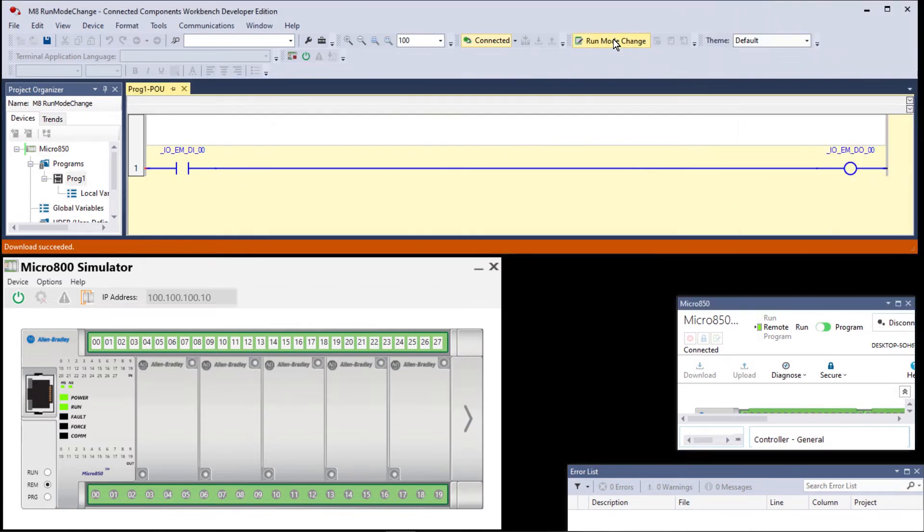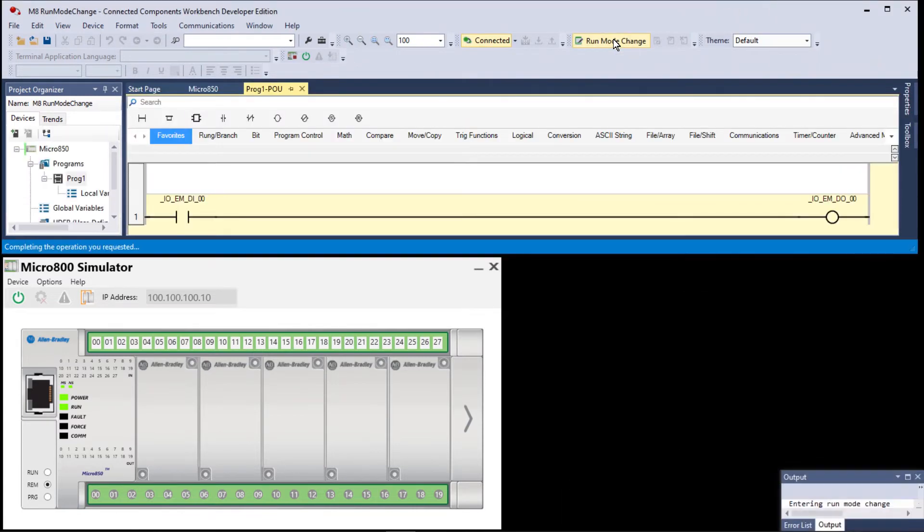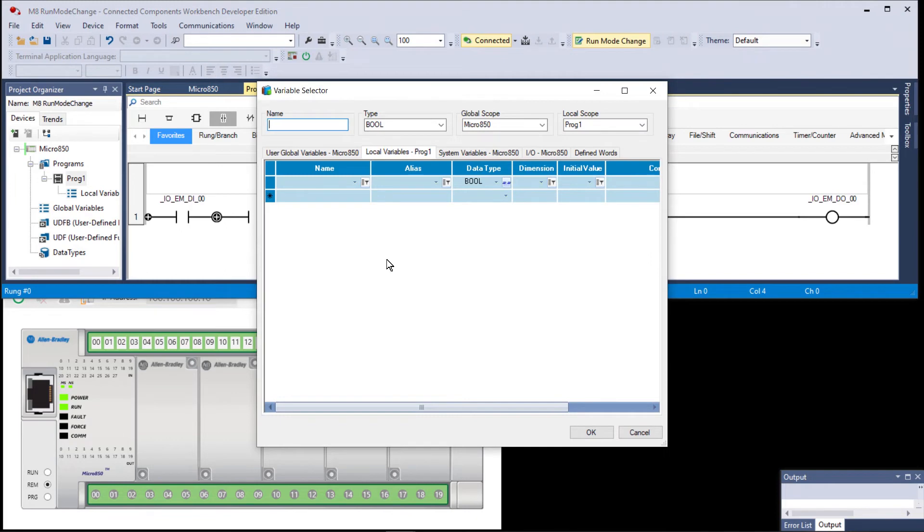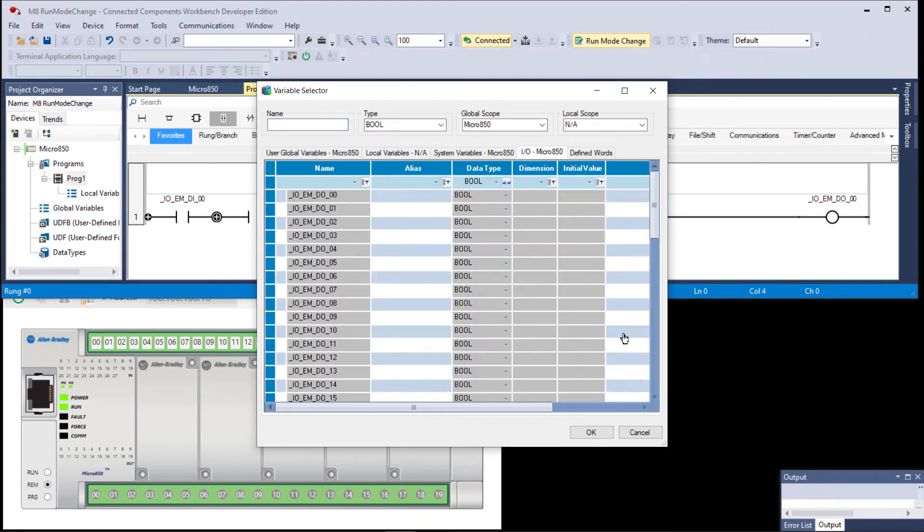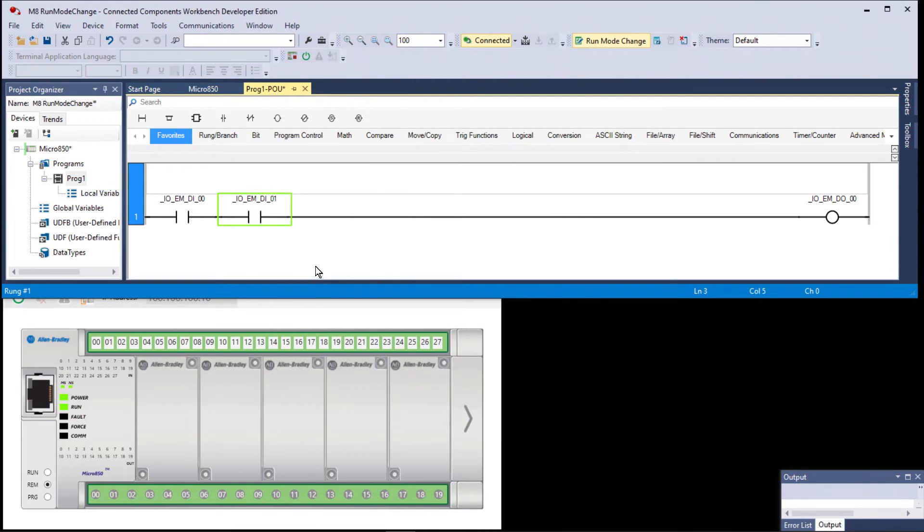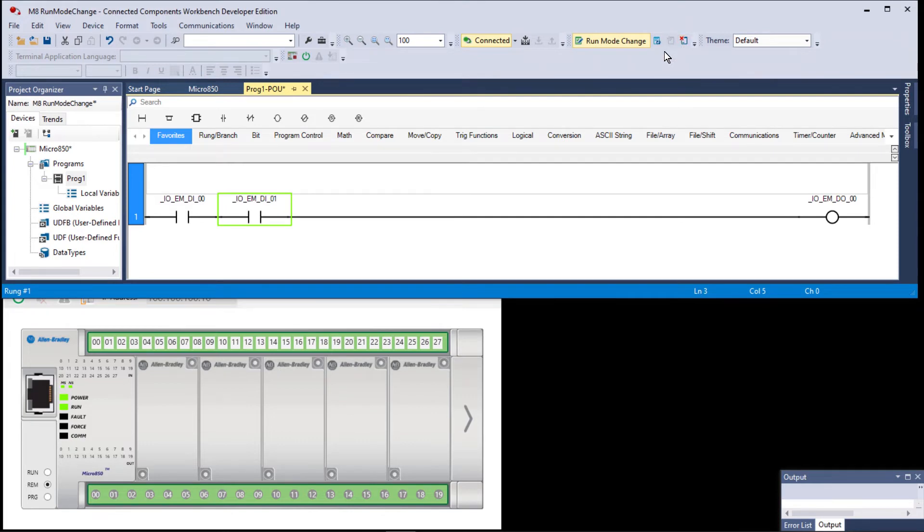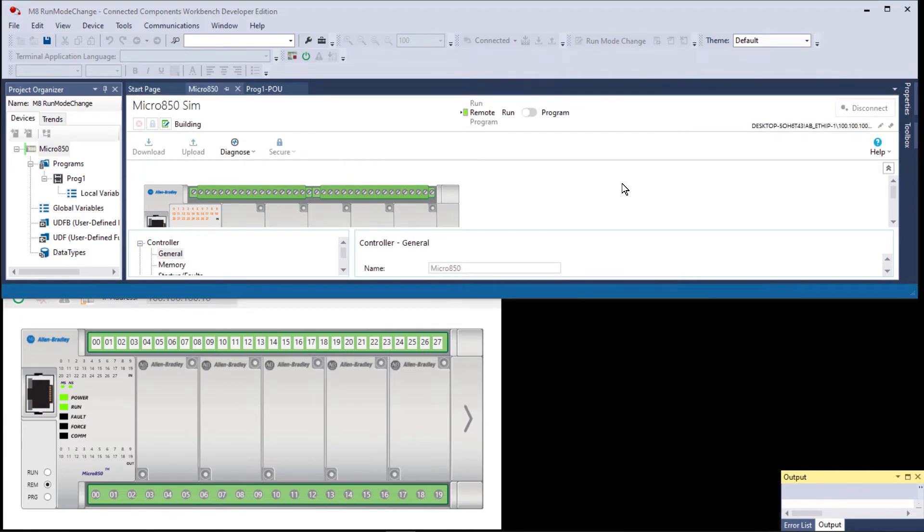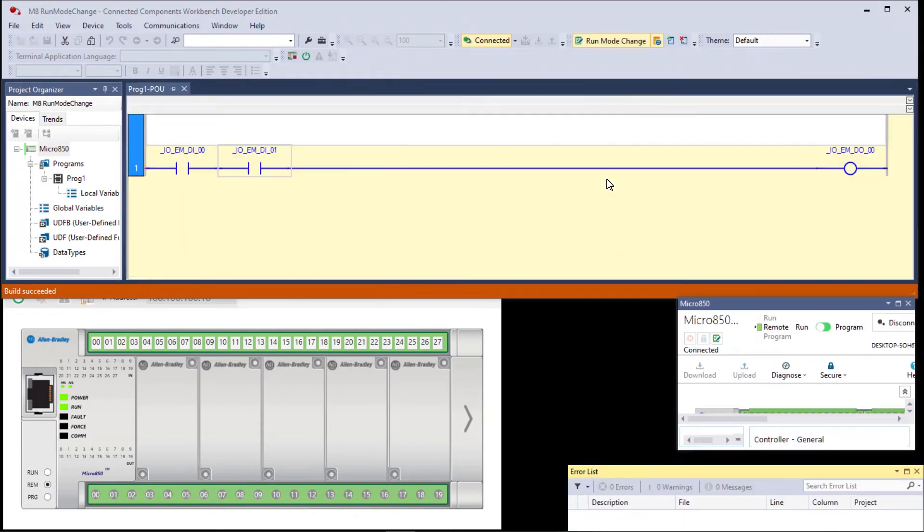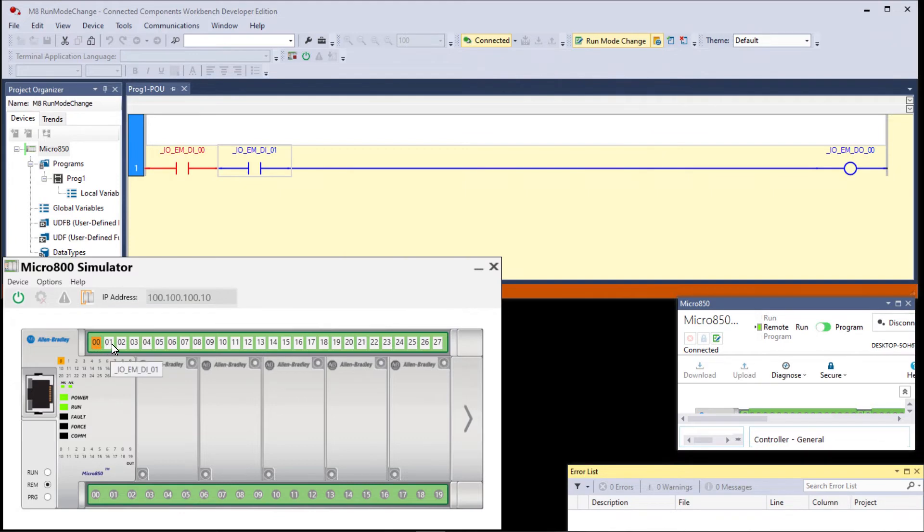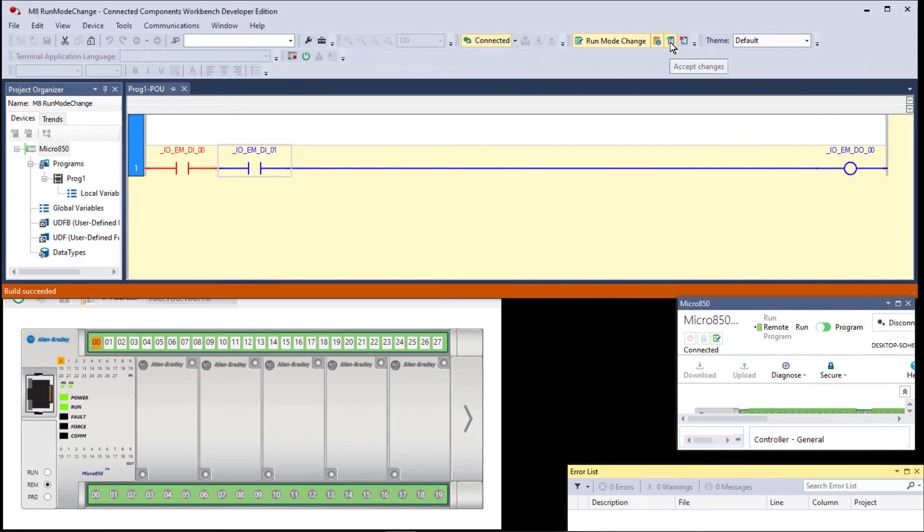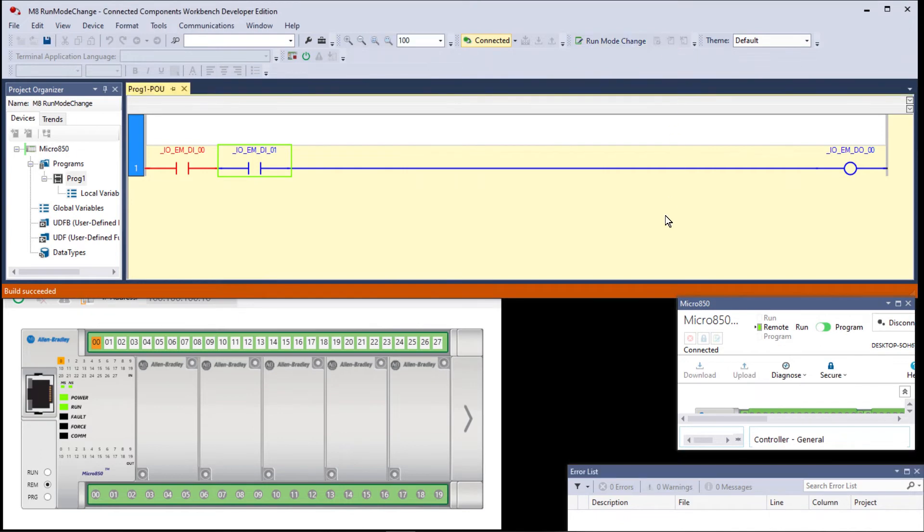So we click on run mode change and that looks like we're offline. We add in another instruction—in other words, we're editing online—and we'll make this one digital input one. At this point we can test the changes or we can cancel the changes. So let's test the changes. It should return to the ladder logic automatically when it's done doing the build and the setup. So we test the changes, turn on input zero, turn on input one, and output zero goes on and off. So we're happy with our changes. We look at our choices again—we are in test. We can accept the changes or again we can cancel. So let's accept the changes and there we are.